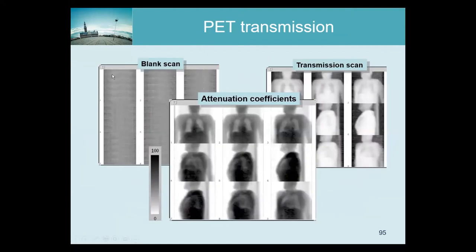The blank scan in this case is not uniform. The whole sinogram, or almost the whole sinogram, is irradiated, but not uniformly. According to the PET scanner, the acquisition looks like a ring, because during one scan the source is rotating all the time. The PET measures the average, so it's the same as the forward projection of a ring, which is not uniform because LORs going through the sides of the ring see more activity than those going through the center.